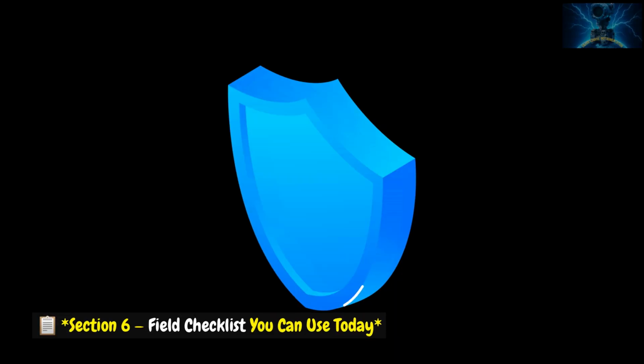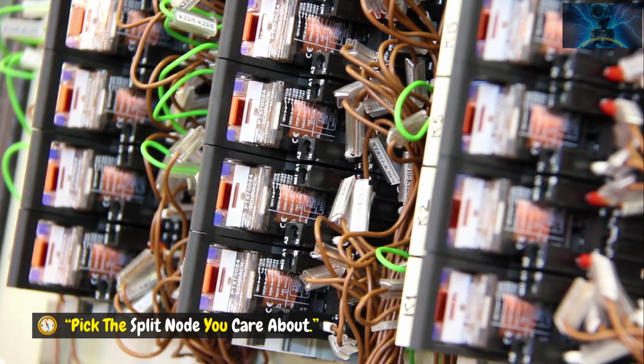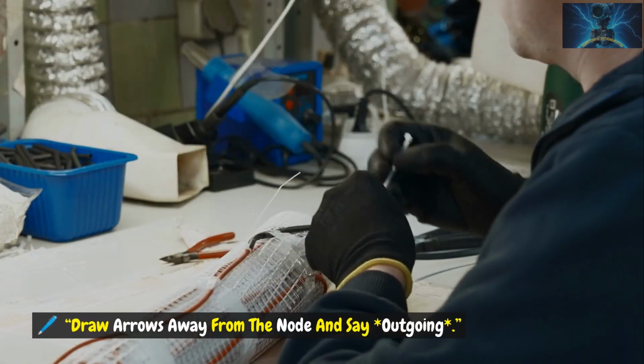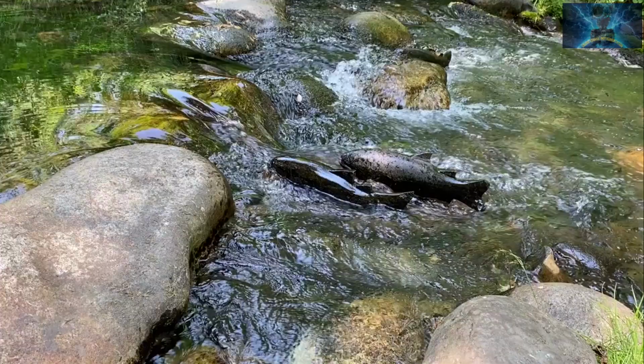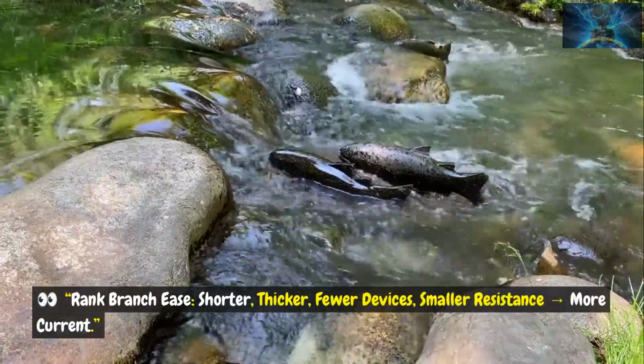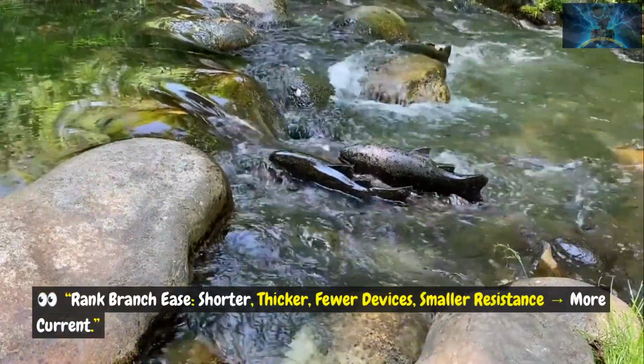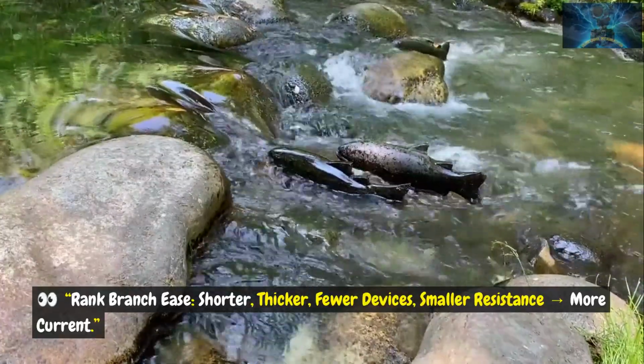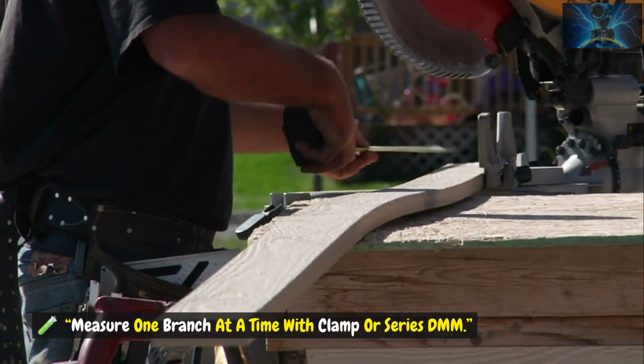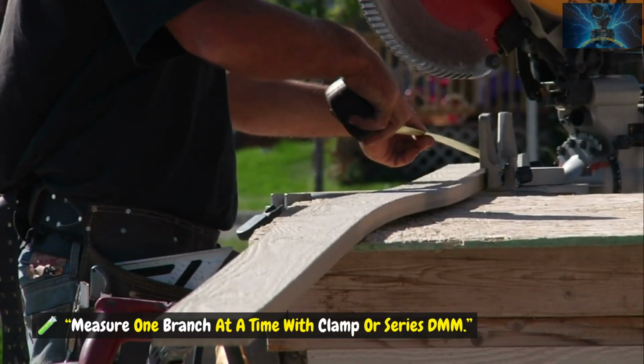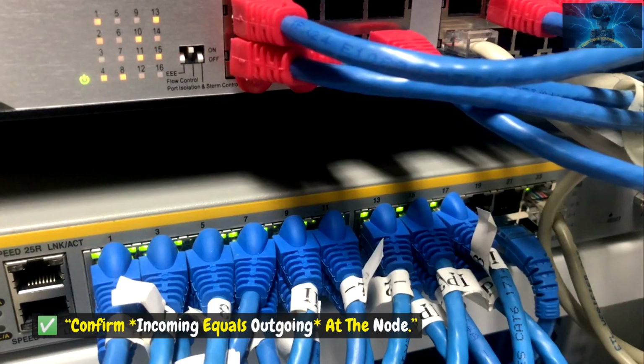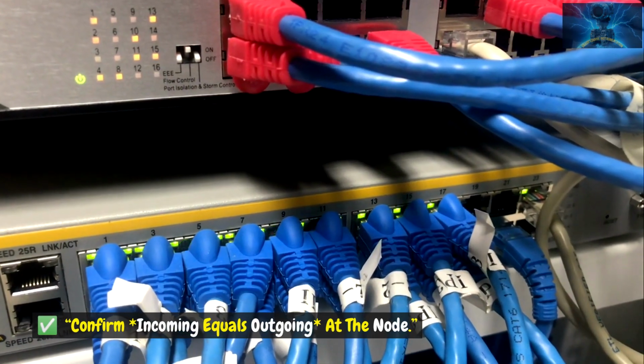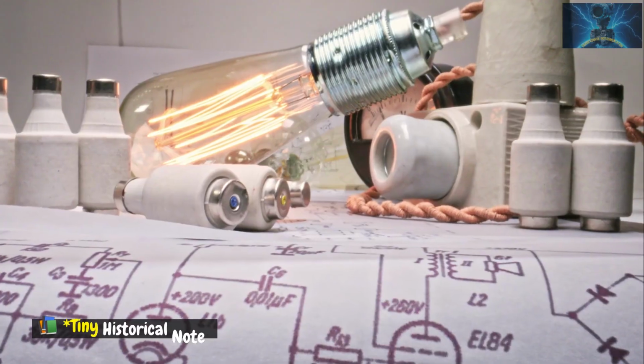Section 6. Field checklist you can use today. Pick the split node you care about. Draw arrows away from the node and say, outgoing. Rank branches: shorter, thicker, fewer devices, smaller resistance, more current. Measure 1 branch at a time with clamp or series DMM. Confirm incoming equals outgoing at the node.